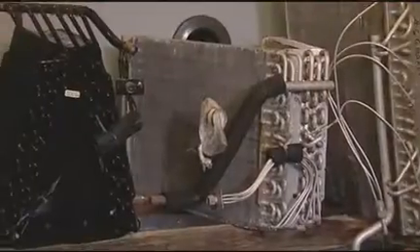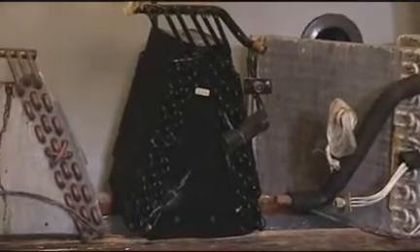Would you like to see our large corrosion chamber? Oh, I absolutely would. Well, it's over this way. So Mark, this is our large corrosion chamber. In here we can pretty well duplicate whatever environment we're trying to qualify a product for. So you can literally test full AC units in here, correct? If you need to. Yeah, we can actually run them while we're testing them. And as you can see, we've got various components in here, and as it clears a little bit, you'll see some in the background, testing various types of coil coatings, testing aluminum coils, those types of things. So should I stop breathing this stuff in? Yeah, you probably should.